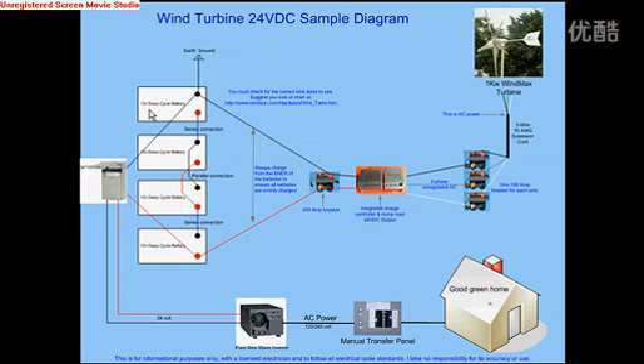So for example, if this battery was 100 minute reserve capacity, and this one was 100 minute reserve capacity, when you go into a series connection, you double the voltage from 12 to 24. The reserve capacity remains the same. So this bank is a 100 amp bank, just as this one will be another 100 amp bank. So we connect them in parallel, and the parallel connection leaves the voltage the same. We have one bank of 24, another one of 24, the total bank voltage is 24. However, the reserve capacity went from 100 amps in this bank plus 100 amps in this bank to 200 amps, which is double that capacity.